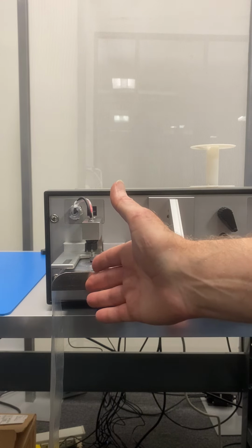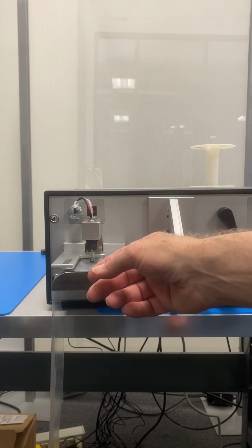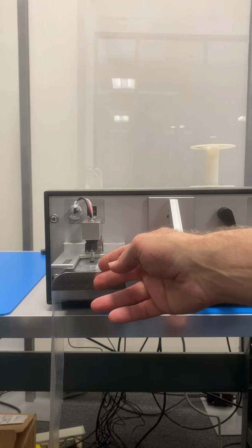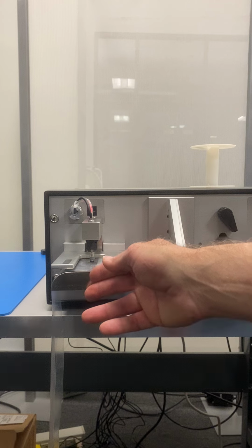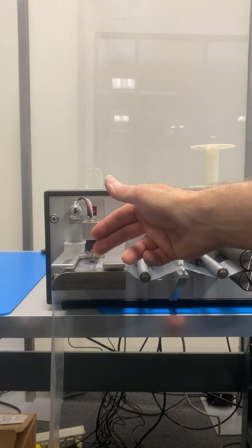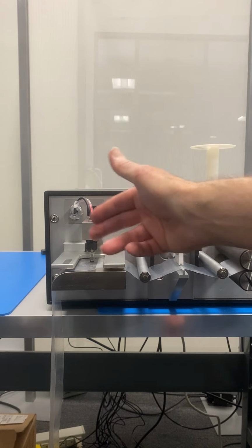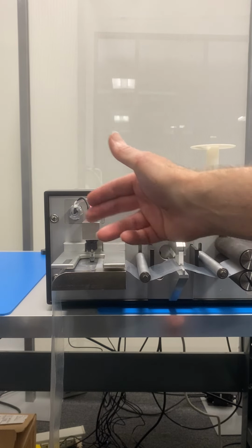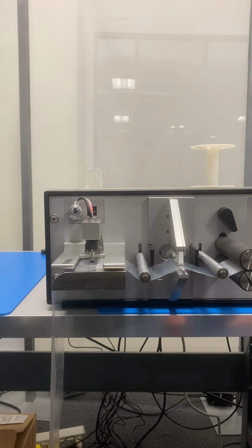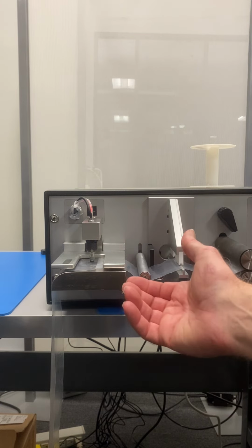We do have a built-in dwell time if you have soft materials and you want the sensor to rest on the film before taking the reading for a certain number of seconds. Contact head lifts up, film advances to the next spot, contact sensor takes a reading, advances, takes a reading, advances, takes a reading, all the way to the end of the sample, and when it reaches the last point, you would likely just stop the drive. There is a cutoff function too that once your film thickness drops below a certain value, it would not recognize the data if the film happens to run all the way out from underneath the contact probe.